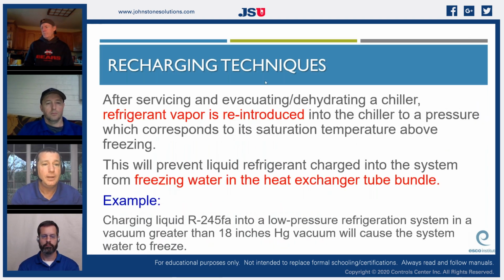Now, if servicing or evacuating a chiller, refrigerant vapor is reintroduced into the chiller to a pressure which corresponds to a saturation temperature above freezing. So you just look at your PT chart for whatever refrigerant you're using and go, okay, at this refrigerant at 33 degrees is this pressure. Well, when I'm charging this system, I actually want to introduce vapor first to get up to that point. That way I'm not introducing liquid in there, because what's going to happen when I put that liquid in? It's going to boil and it would freeze my water. It's all about keeping that water from being frozen.